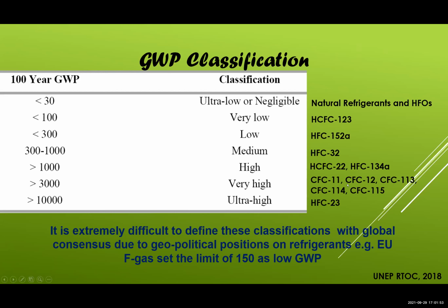And most of the CFCs, you can see from here, are all very high, above 3,000. And HFC 23 is the ultra high, but that is not used in a major way in air conditioning and refrigeration, except as a blend. It comes out as a co-product when you make R22. So 23 was used once upon a time, but now it is not used. So we'll be talking mostly about these refrigerants, including HFOs.